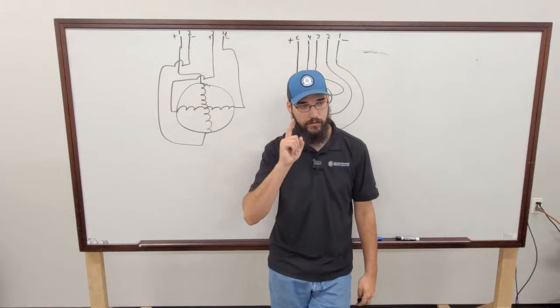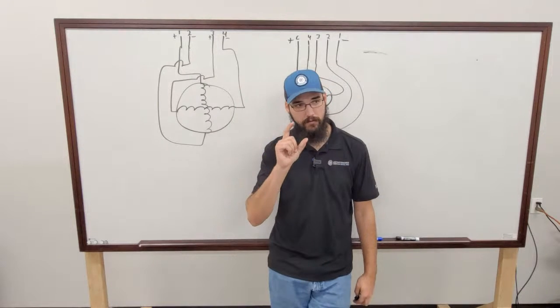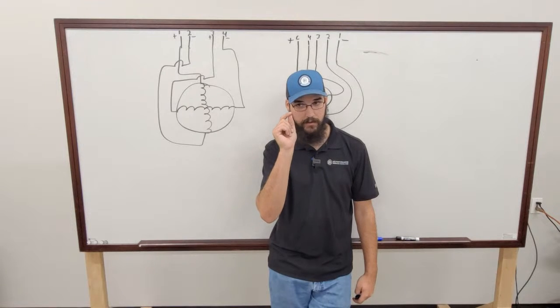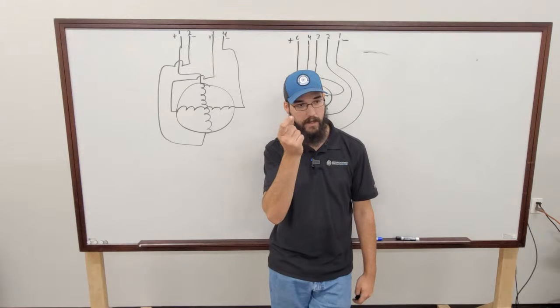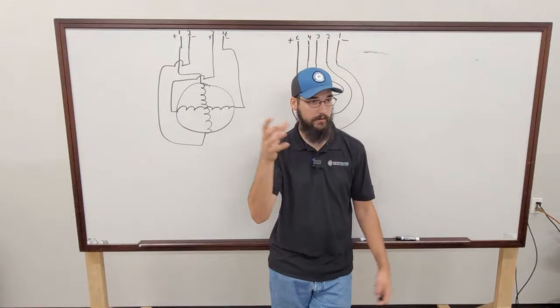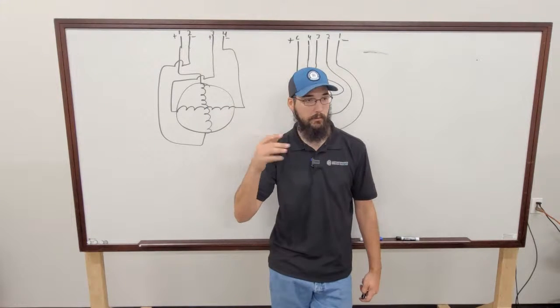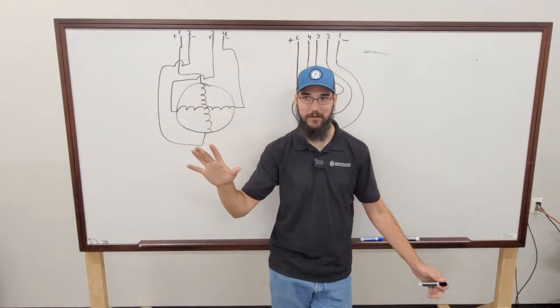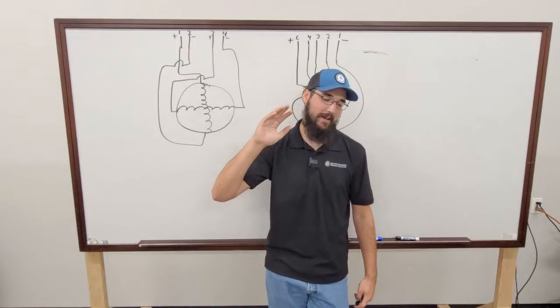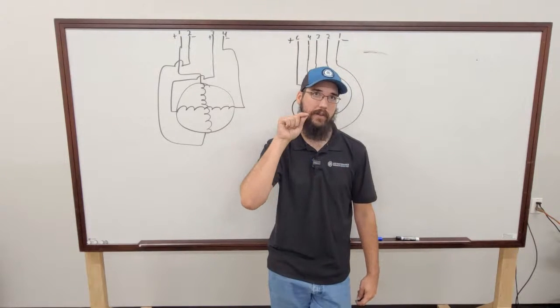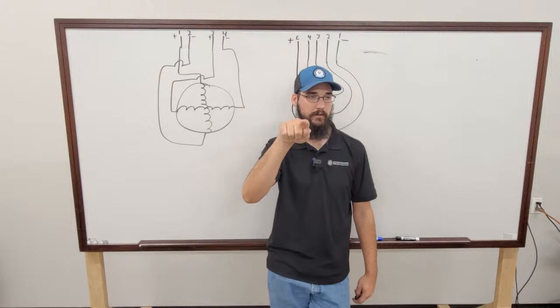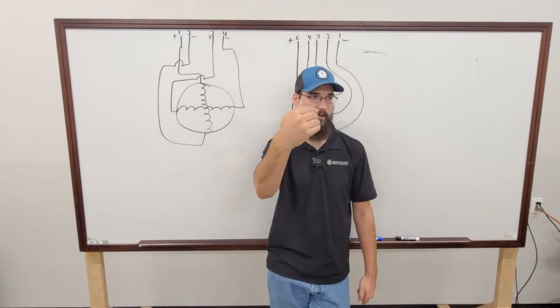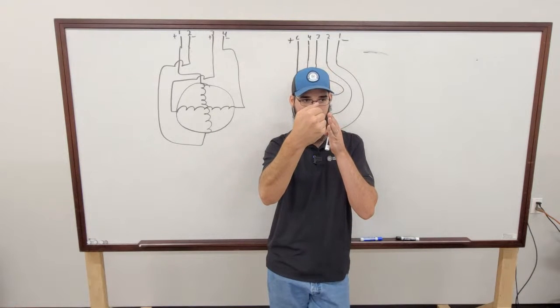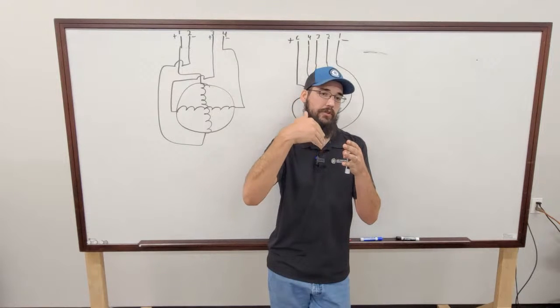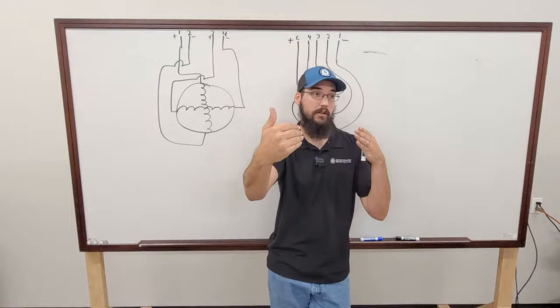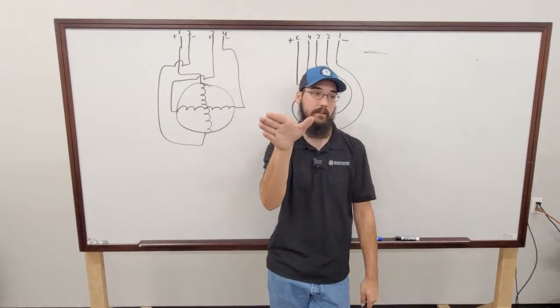The critical thing is that those matter what direction they're facing. If you ever look at one of those little flow sensors, there's a divot in the head of it, where you would put your hex head, whatever, right? It's a good place for the channel locks. That's a joke, everybody. It's a joke. Please don't. Anyway, that divot should be facing into the flow of the water. So against the flow, right? So if the water's coming this way, your flow sensor should be on the leaving side of the machine, which means that basically that little dot should be facing the machine.